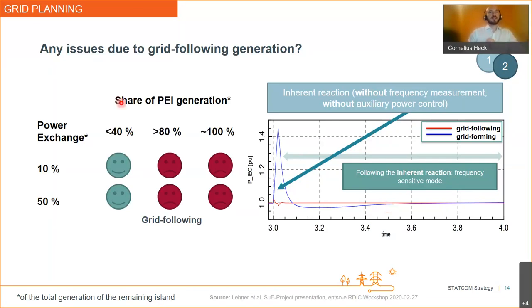So what we see here is how much power electronic interface generation we have, as share of the total generation in any remaining island, so for example, the green island that we've seen a few slides ago. And then how big of a power exchange could it be? So 10% or 50% of the total generation. And as long as we stay below a threshold of up to 40% of grid following devices that make up the total generation of one island, a power exchange of up to 50% seems feasible. At least in our studies, it was feasible.